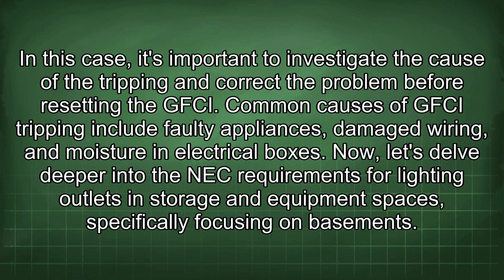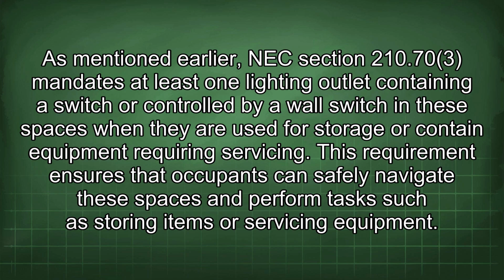Now let's delve deeper into the NEC requirements for lighting outlets in storage and equipment spaces, specifically focusing on basements. As mentioned earlier, NEC Section 210.70(3) mandates at least one lighting outlet containing a switch or controlled by a wall switch in these spaces when they are used for storage or contain equipment requiring servicing. This requirement ensures that occupants can safely navigate these spaces and perform tasks such as storing items or servicing equipment.